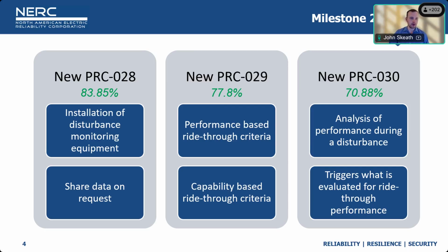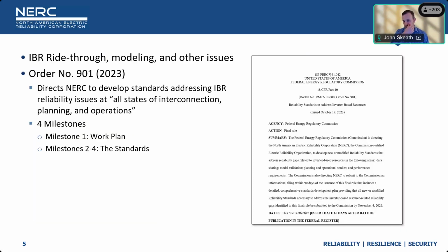Let's start where it is probably best to start, in the beginning. I set the context that this standard was developed with Order 901, and FERC Order 901 identified that IBR ride-through models and additional issues in planning and studies dominated the IBR fleet. This was released in October of 2023 and directed NERC to develop specific standards to address the reliability issues at all stages of interconnection, planning, and operations. I overviewed those 4 milestones: one was the work plan, and milestones 2 through 4 being those particular standards.